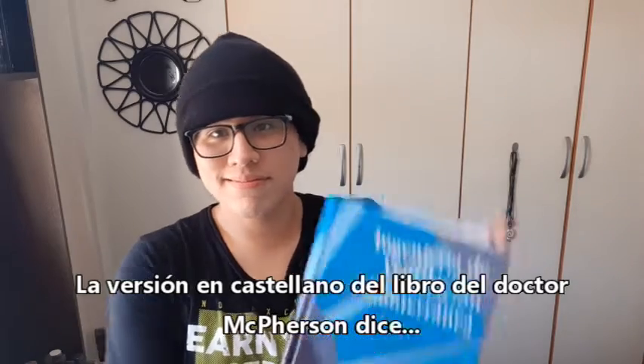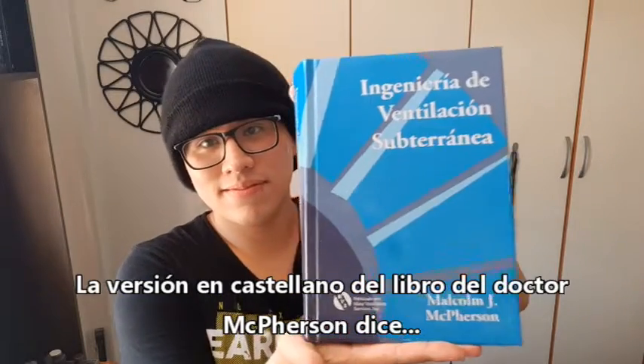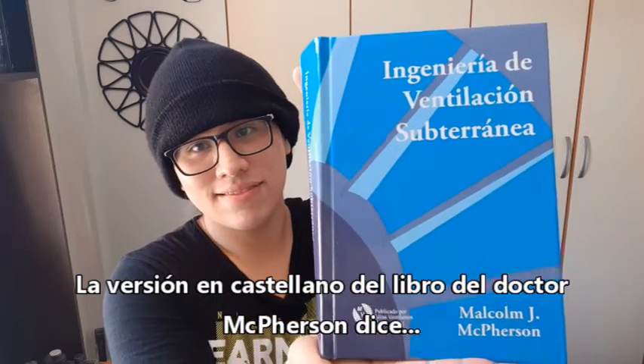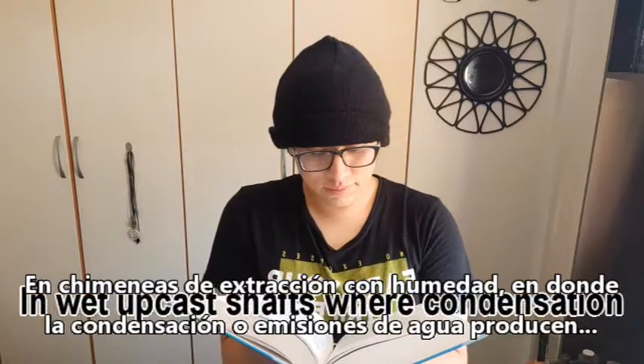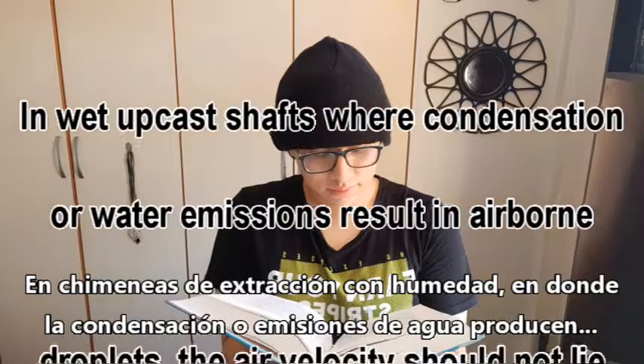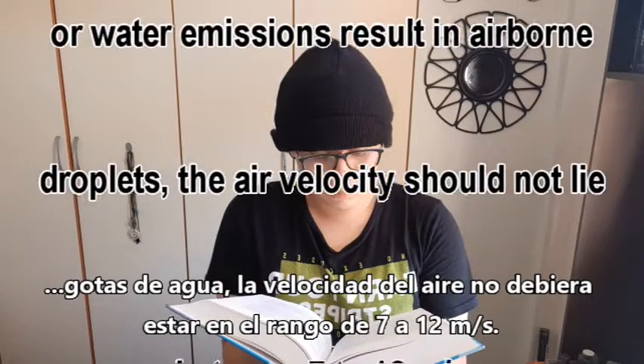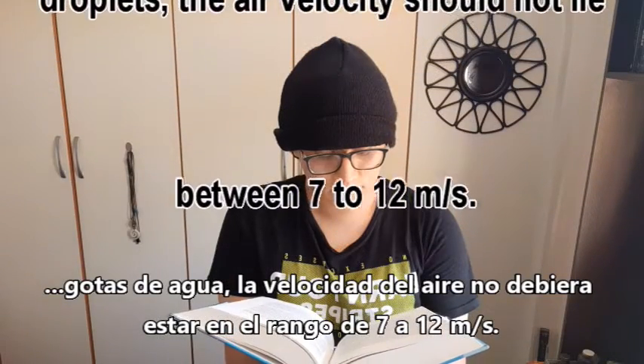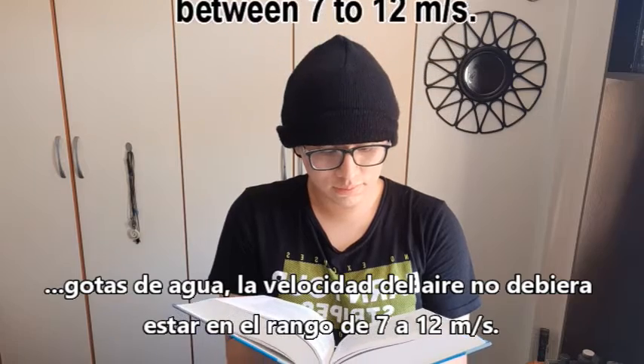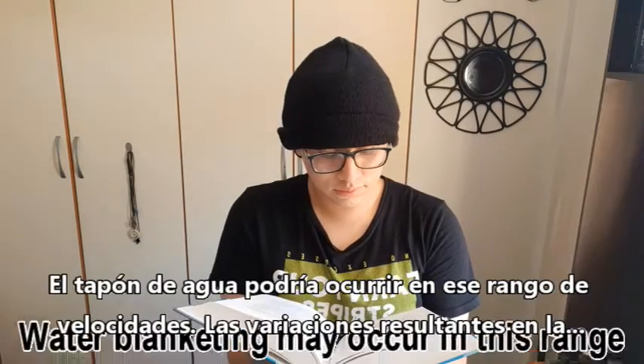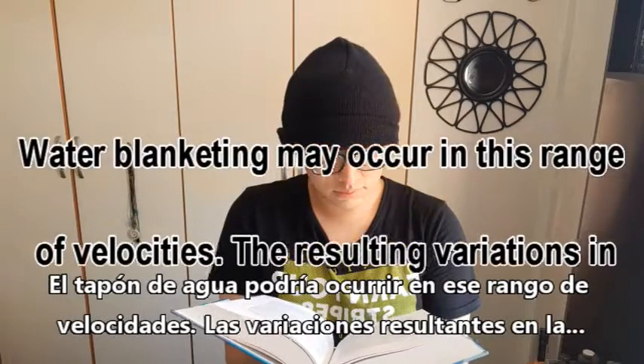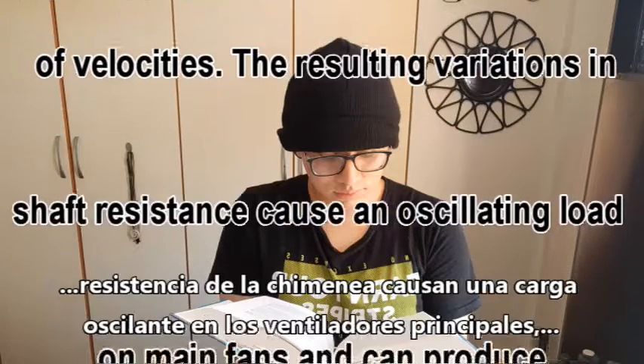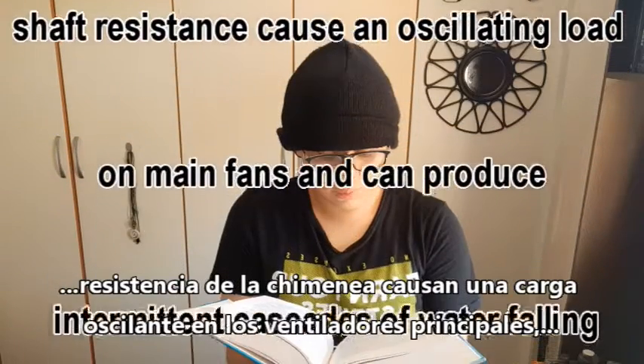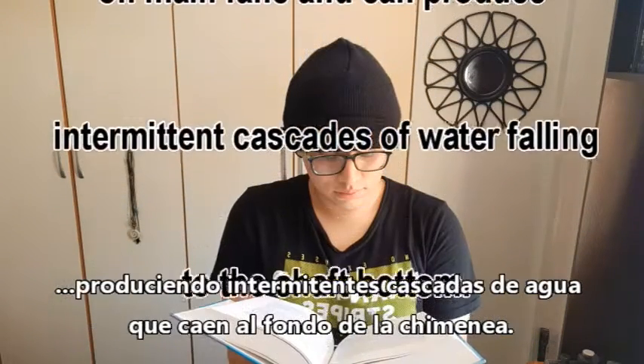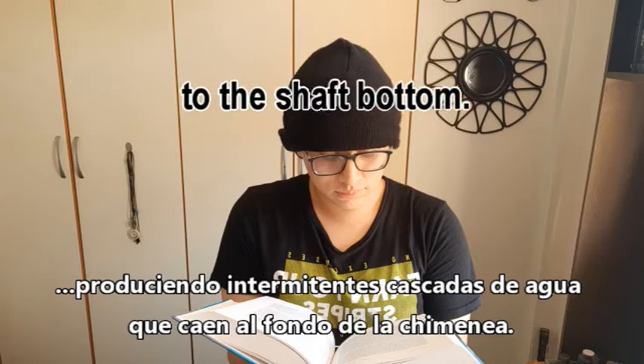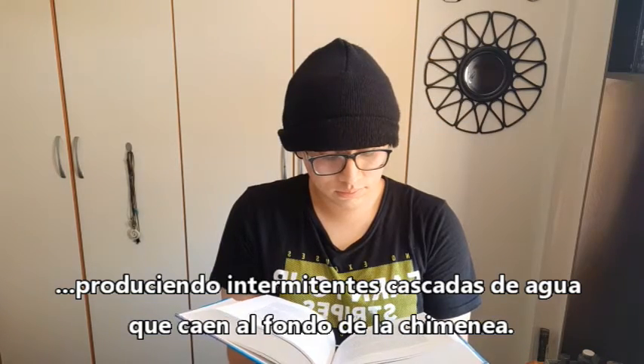This book here, this is the Spanish version of the Macpherson book, says in wet upcast shafts where condensation or water emissions result in airborne droplets, the air velocity should not lie between 7 to 12 meters per second. Water blanketing may occur in this range of velocities. The resulting variations in shaft resistance cause an oscillating load on main fans and can produce intermittent cascades of water falling to the shaft bottom.